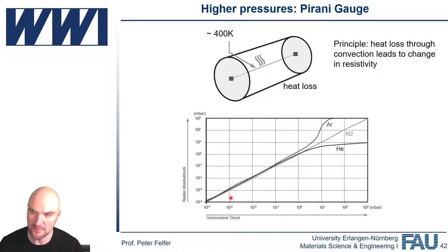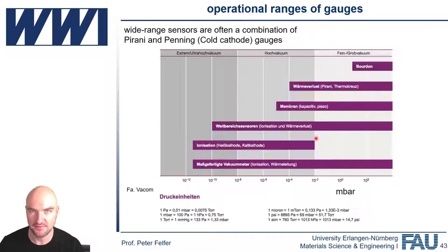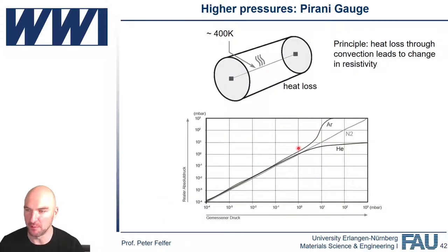These days, there are schemes like micro-Pirani gauges and ramping Pirani gauges that can get it down to 10 to the minus 4 to 10 to the minus 5 millibars. What would be really nice is if Pirani gauges could get down to 10 to the minus 6, but that doesn't seem to be anywhere on the horizon. But 10 to the minus 5, MKS makes Pirani gauges that go down to that, which can be good enough for a load lock. The good thing here is they're extremely robust, so you can have an inrush of air and they're not going to care very much.